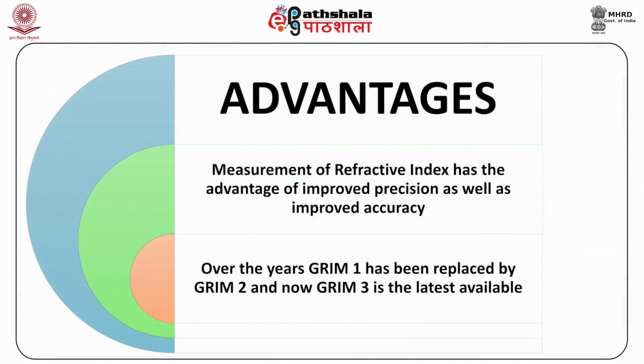Now, in this method also, there are some advantages as well as some limitations. Advantages are as follows. Now, the automated method for measuring refractive index has the basic advantage of improved precision as well as improved accuracy. The refractive index is automatically generated here in this method and electronically recorded. Over the years, GRIM1 has been replaced by GRIM2 and then by GRIM3, which is the latest available.